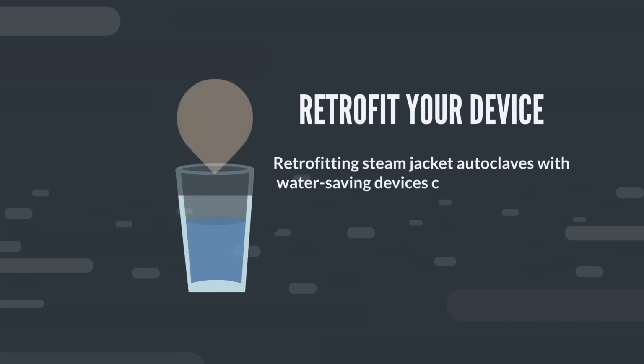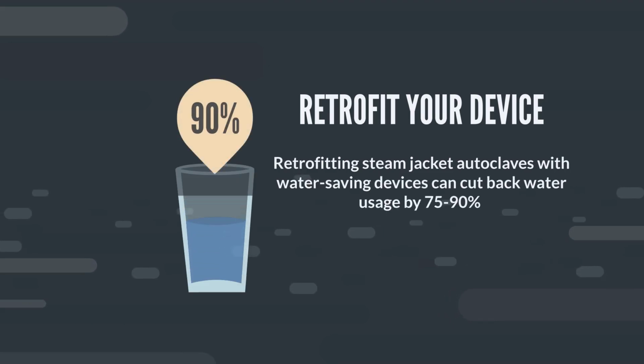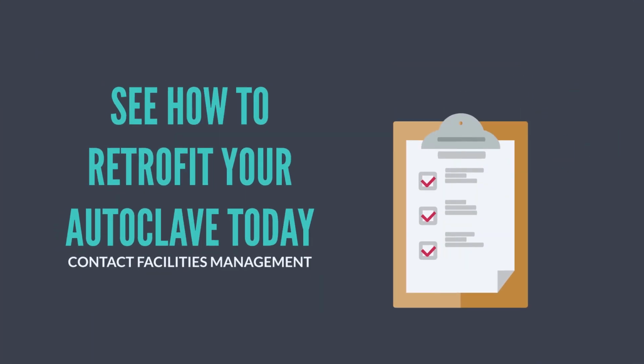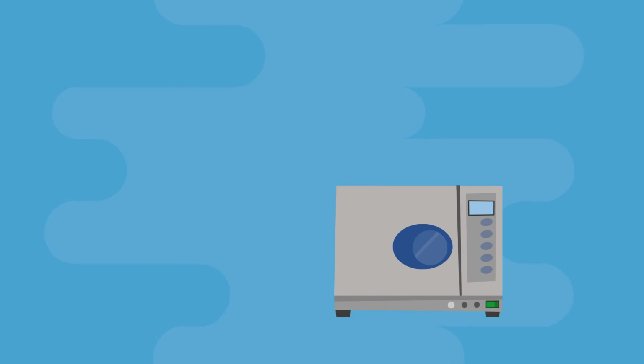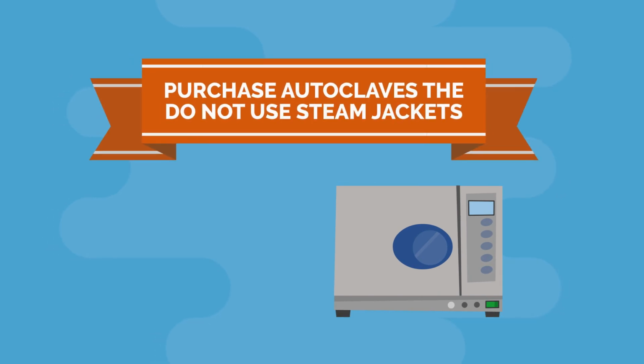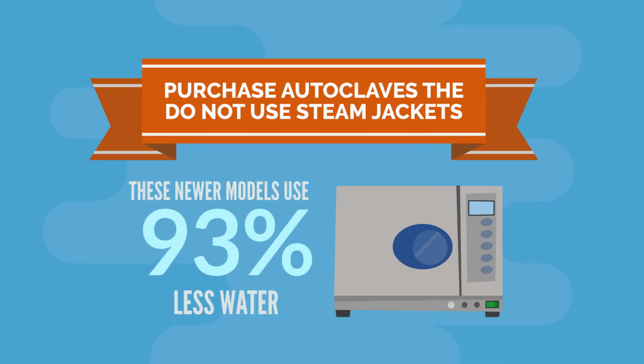Retrofitting steam jacket autoclaves with water-saving devices can cut back water usage by 75 to 90%. That's huge. Add this effective water-saving action to the top of your to-do list. If your lab is in the market for a new autoclave, consider purchasing research-grade autoclaves that do not use steam jackets. These newer models use 93% less water and help reduce energy consumption.